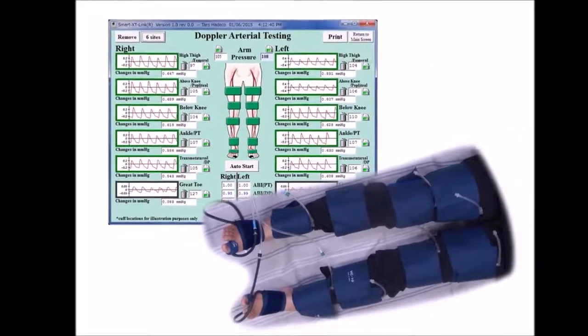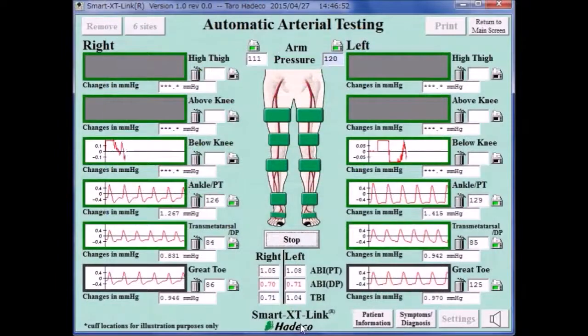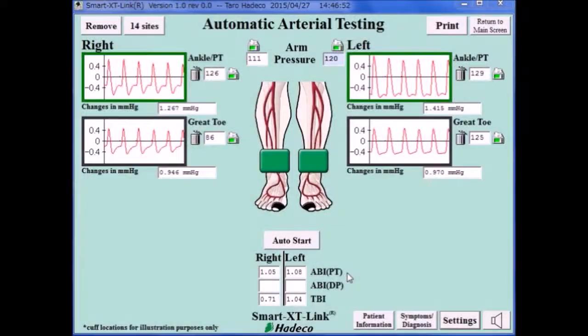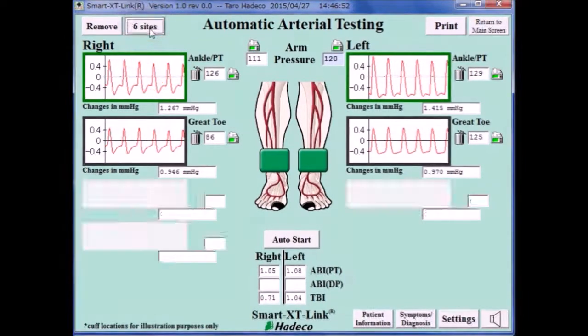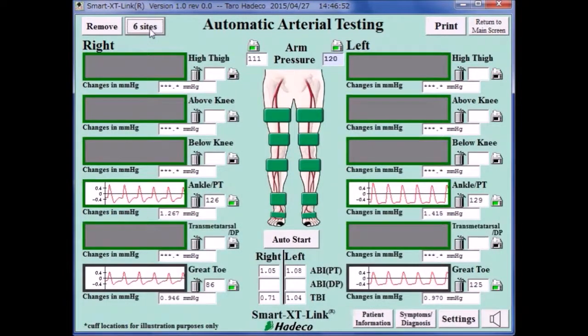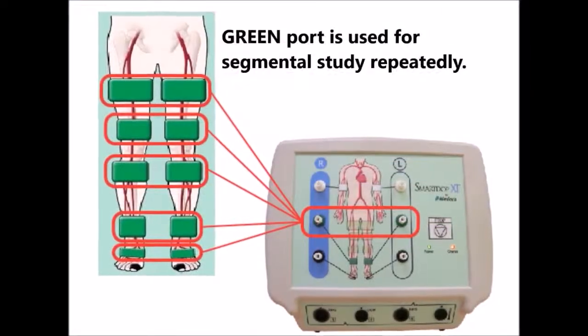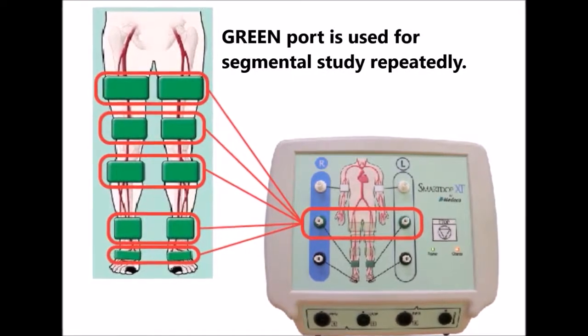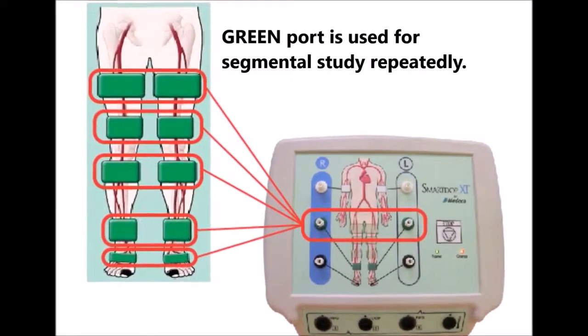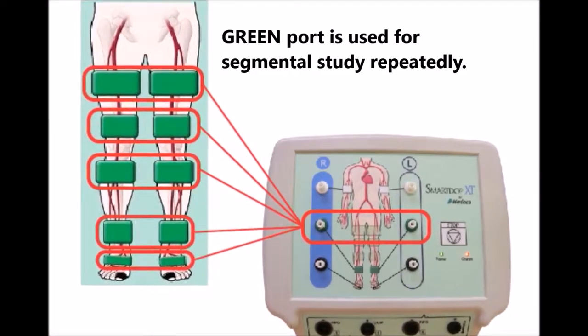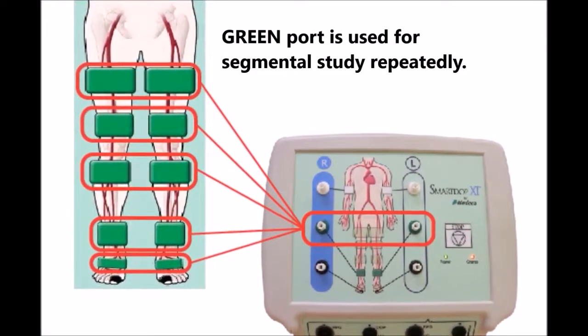If desired, further segmental pressure studies can be done on a rolling basis for up to 14 sites on both the automatic and Doppler arterial testing screens. To enable the 14 sites, click the 14 sites button on the test screen to expand from 6 to 14 sites for segmental studies. The two green ports originally used for the ankles will be repeatedly used for each segmental study for the remaining sites, one after the other.